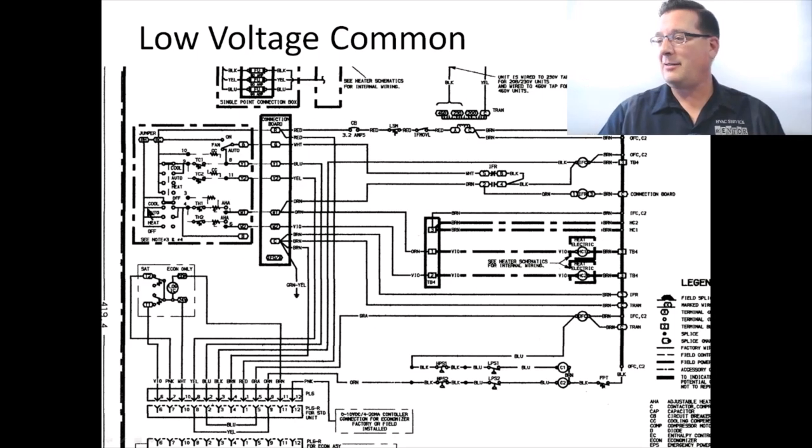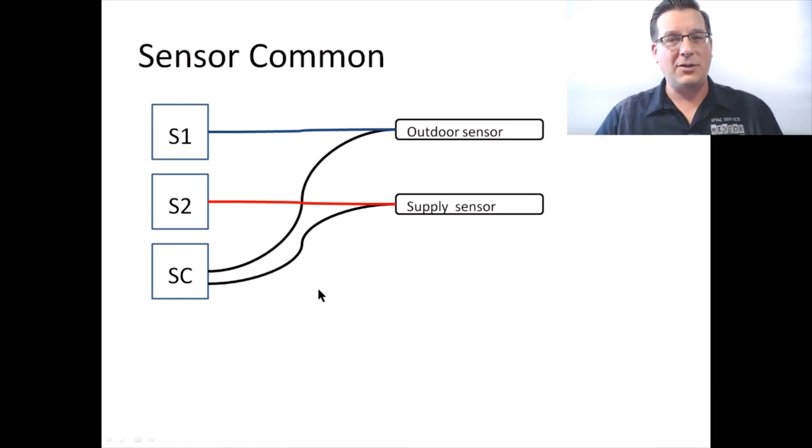The last common designation of the term common is what I call a sensor common. Some electronic controllers and electronic circuit boards take information from analog sensors, very commonly temperature sensors. Boiler outdoor reset controllers do this quite a bit, where there will be an outdoor air temperature sensor and there will be a supply water temperature sensor and the controller needs to reference both of these temperatures to make decisions about how it adjusts the temperature set point of the boiler. So there are two sensors and there are three terminals that these sensors connect to. Sensor one, which is meant to be the outdoor sensor, sensor two, which is meant to be the supply water sensor and sensor common, which means that the other two wires of each sensor both land on a common terminal. Both sensors share this terminal in common with one another.